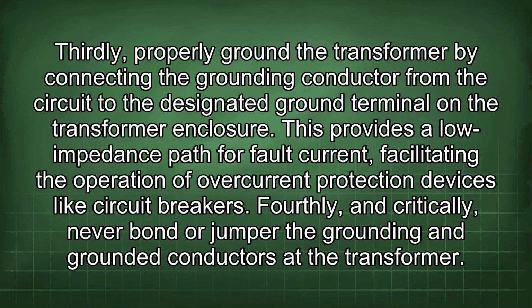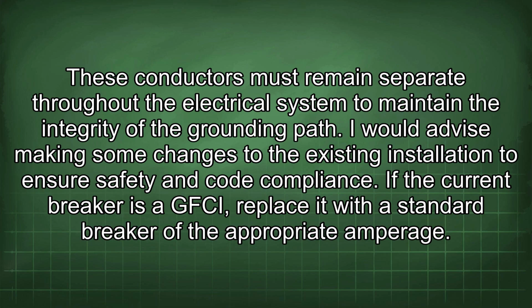and the transformer enclosure. This provides a low impedance path for fault current, facilitating the operation of overcurrent protection devices like circuit breakers. Fourthly, and critically, never bond or jumper the grounding and grounded conductors at the transformer. These conductors must remain separate throughout the electrical system to maintain the integrity of the grounding path.